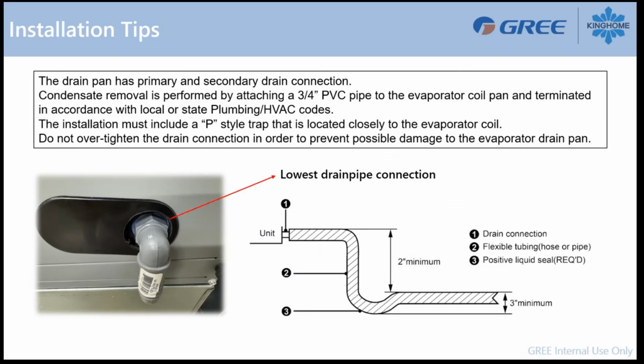Also, because the coil is installed below the blower motor, the coil is in a negative pressure. So talking about the drain, you will have to do a P-trap to catch the condensate water and make sure it will drain properly. So the P-trap needs to be located close to the coil, or as close as possible to the coil, and make sure the drop respects the 2 inches minimum to hold a quantity of water, to not let the air handler suck air from the drain. So this is really important to have a good drain evacuation.